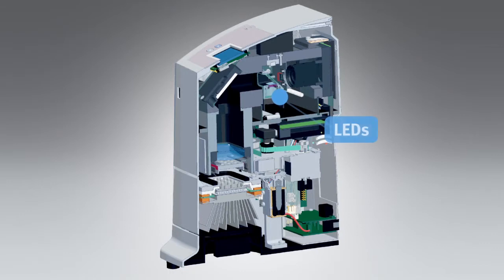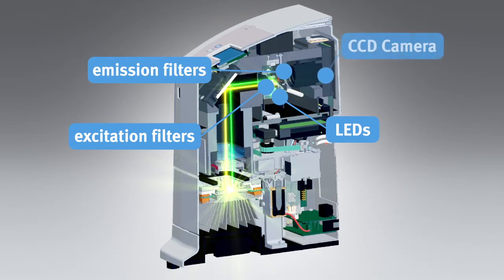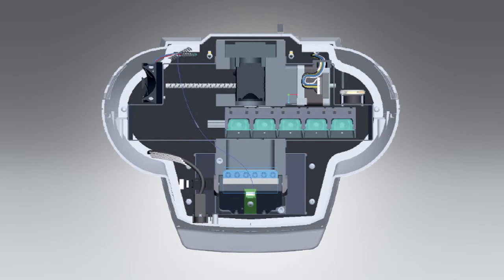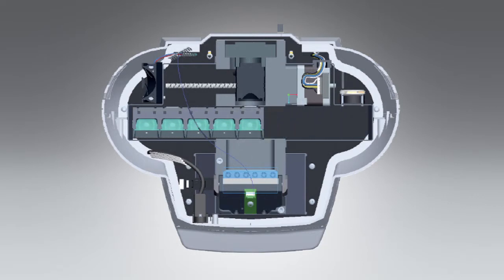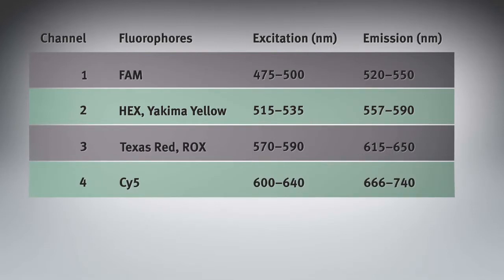The optical system in PikoReal consists of 5 LEDs, excitation and emission filters, and a CCD camera. The optic shuttle contains separate optical components for each of the 5 channels. Up to 4 targets can be multiplexed using channels 1 to 4, while the 5th channel is dedicated for SYBR Green and high-resolution melt experiments. The system comes with a color calibration utility for customizing and adding new dyes.